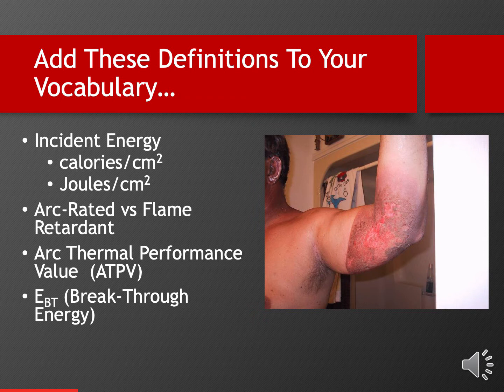That is the blast component of the arc. And so, of course, with arc blast energy the way it is, getting an arc flash going could blow normal clothing right off of your body, leaving you unprotected from the arc flash hazards that are there. And so, of course, arc-rated clothing needs to be strong enough to withstand the blast, as well as insulated well enough to protect you from the heat exposure. Let's go to the next slide.